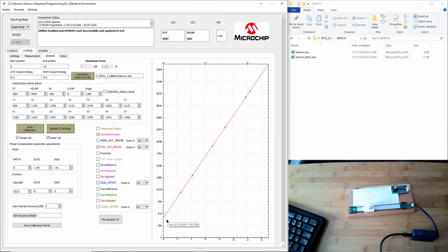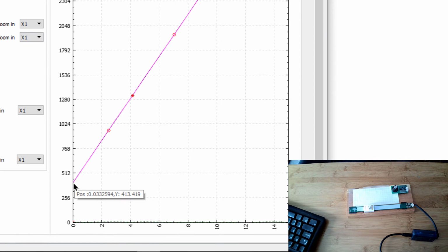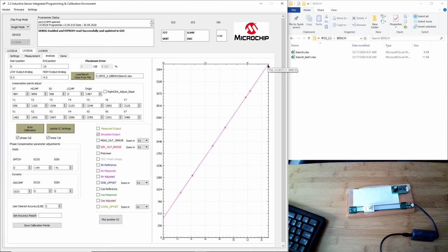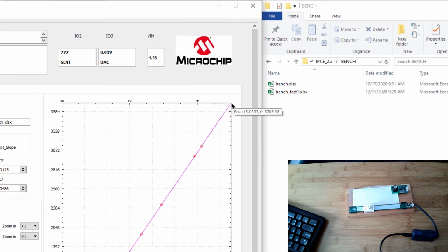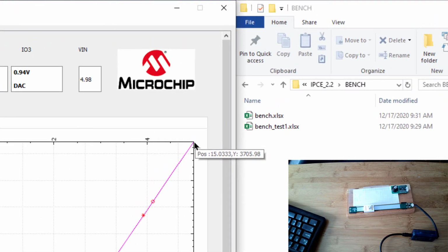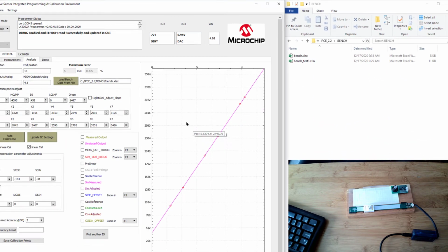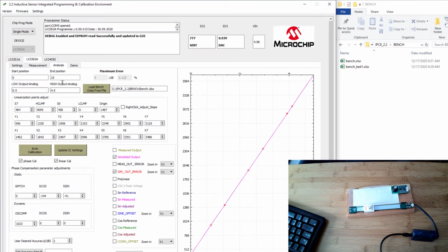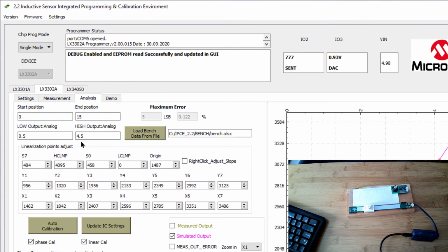But let me show you on the graph one other point, which is that 0 to 5 volts gets mapped over here. If I come down here, I go to this point, this turns out to be 10% of 4096, which is 409, right at that point, which represents 0.5 volts. And then the other one is 90% of 4095, which is up here, about right around 3696, if that's the right number, if my math's correct. And that represents 90%. In this case over here, 4.5 is 90% of 5 volts. Okay, so we're ready to go.